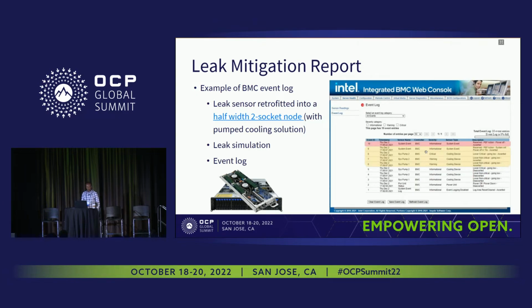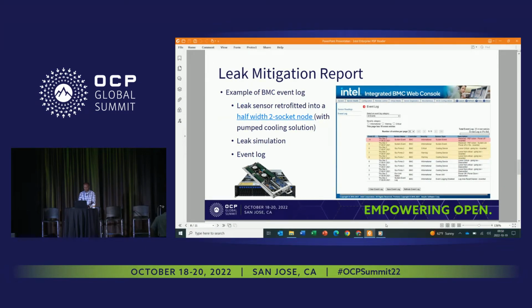So this is an example. I actually took one of these pumped systems, a little pump on top of the CPU. All I did is I kind of cheated, taking off the pump and connecting it to the leak sensor using the same fan header kind of connector. That's why the event log is looking for a pump, but it's actually not a pump, it's the leak sensor. I was artificially simulating a leak, just putting a drip of water. And then this is what the event log looks like. And I do have a little demo I can quickly show.